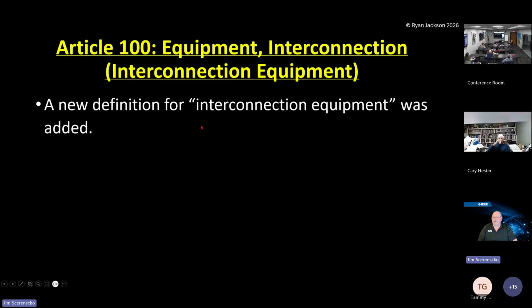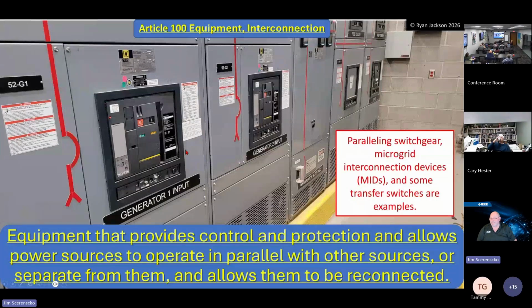Interconnection equipment, a new definition. Equipment that provides control and protection and allows power sources to operate in parallel with other sources or separate from them and allows them to be reconnected. So the paralleling switchgear, microgrid interconnection devices, the MIDs, and some transfer switches are examples.